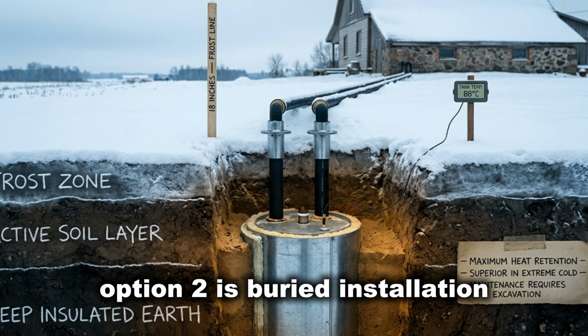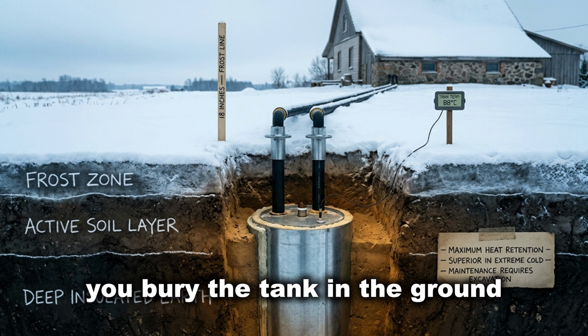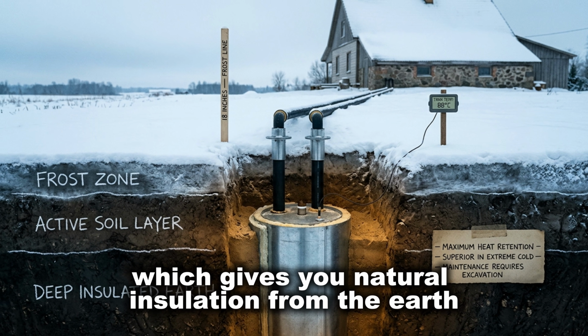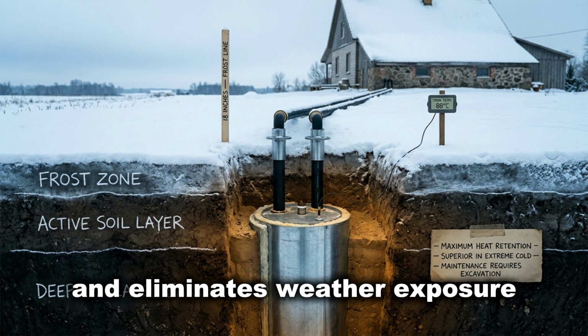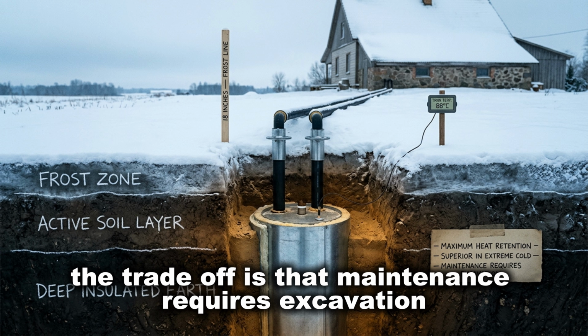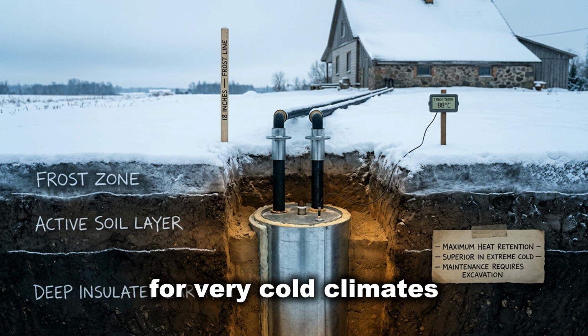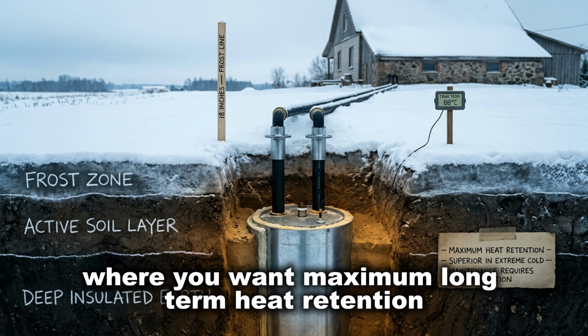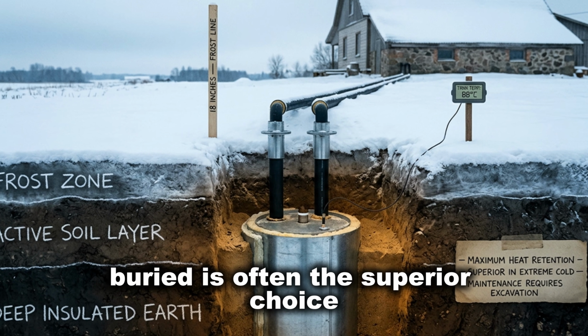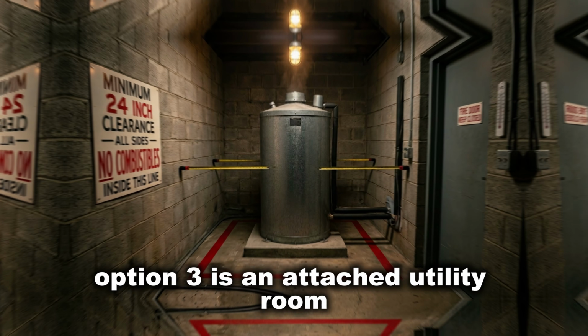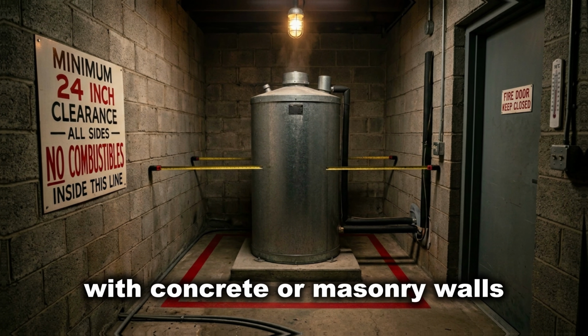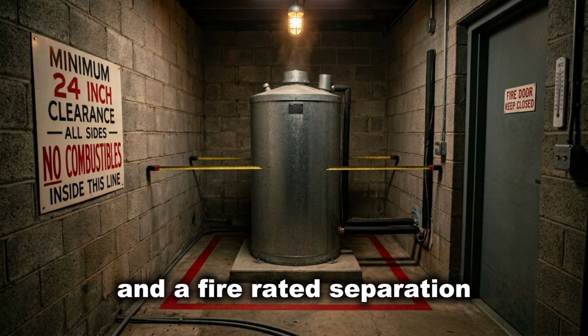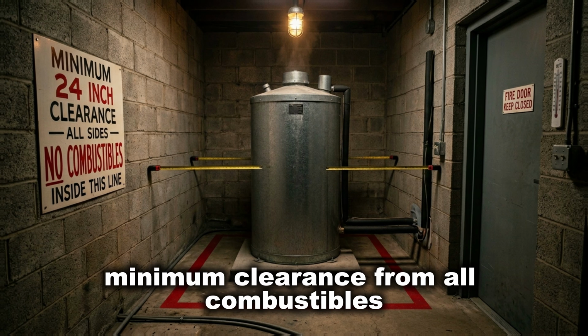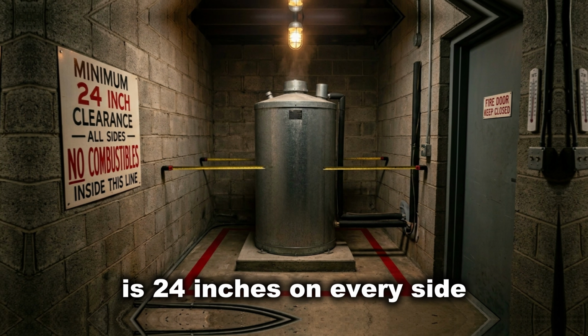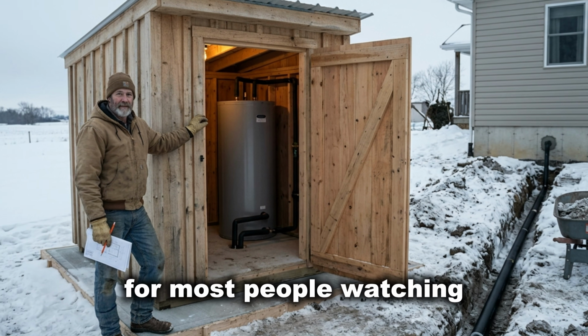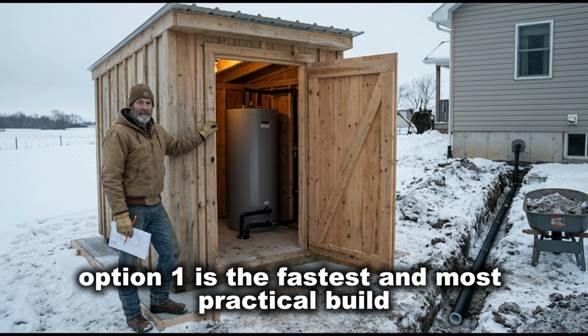Option 2 is buried installation. You bury the tank in the ground, which gives you natural insulation from the earth and eliminates weather exposure. The trade-off is that maintenance requires excavation. For very cold climates where you want maximum long-term heat retention, buried is often the superior choice. Option 3 is an attached utility room with concrete or masonry walls and a fire-rated separation. Minimum clearance from all combustibles is 24 inches on every side. For most people watching, option 1 is the fastest and most practical.